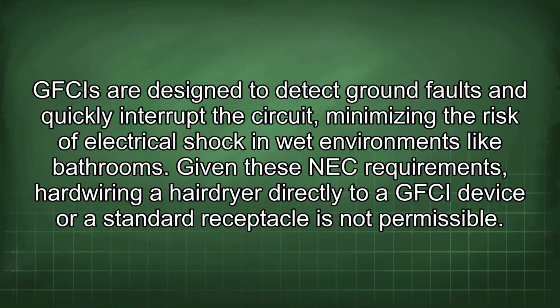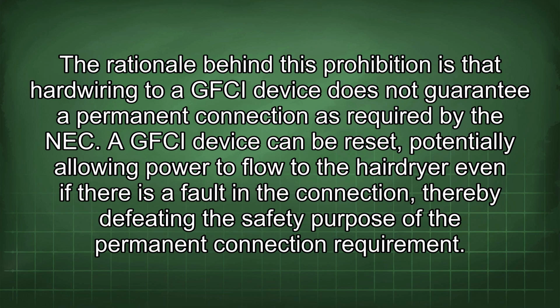GFCIs are designed to detect ground faults and quickly interrupt the circuit, minimizing the risk of electrical shock in wet environments like bathrooms. Given these NEC requirements, hardwiring a hairdryer directly to a GFCI device or a standard receptacle is not permissible. The rationale behind this prohibition is that hardwiring to a GFCI device does not guarantee a permanent connection as required by the NEC. A GFCI device can be reset, potentially allowing power to flow to the hairdryer even if there is a fault in the connection, thereby defeating the safety purpose of the permanent connection requirement.